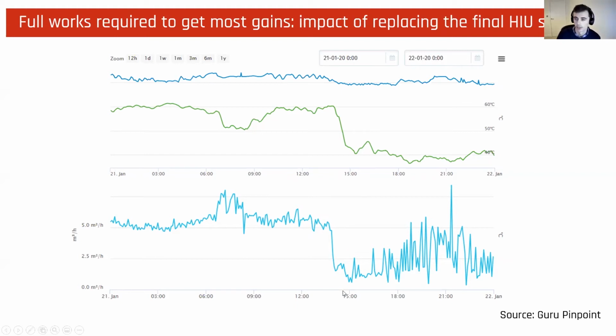At the same time, there's a significant drop in flow rate. And this is great to see because we bring down those heat losses from the network, but also we bring down the pump energy consumption, because as you can see on the light blue line here, the pumps are actually reacting to demand. They're reacting to the flow rate on the network as per the respective hot water and heating demands throughout the day, which wasn't happening before.